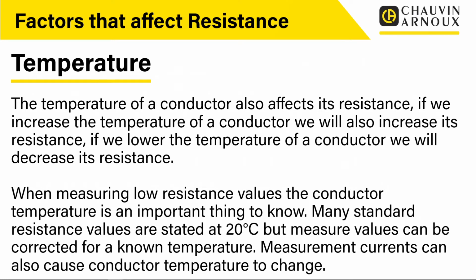Measurement currents can also cause conductor temperature to change. So that's an important thing to be aware of, that by the way we carry out the test, we can actually affect the temperature. So by using a high measurement current, we could actually even heat up the conductor that we're measuring.